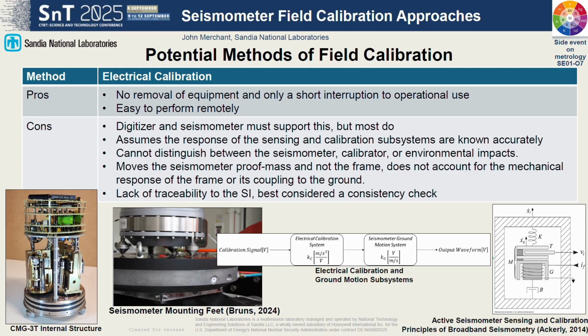And hopefully we're not deluding ourselves too much, because you really can't distinguish between the characteristics of the electrical calibrator, the characteristics of the seismometer, and these issues of the seismometer suspension, because you're actuating the mass and not actuating the case, and it's different parts of the mechanics. And as well, there's no traceability to the SI in this electrical calibration process. So it's an important tool, but it doesn't have traceability.